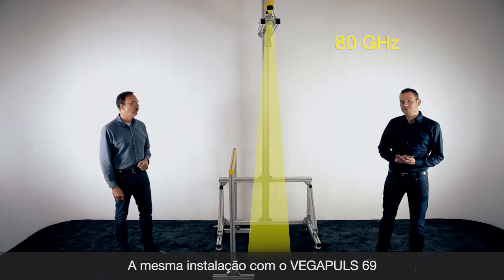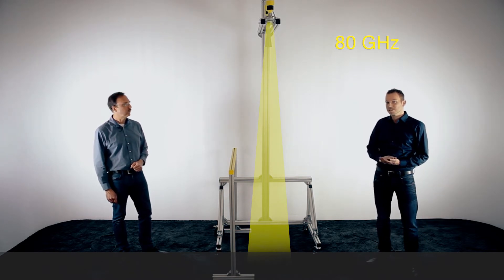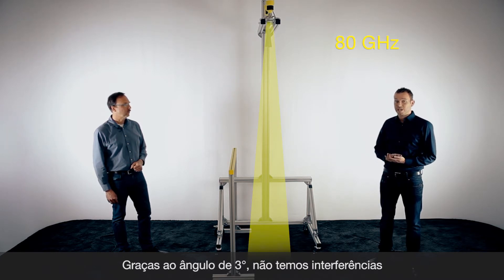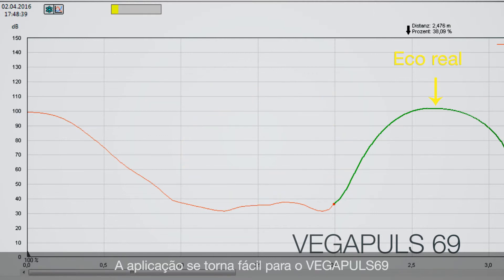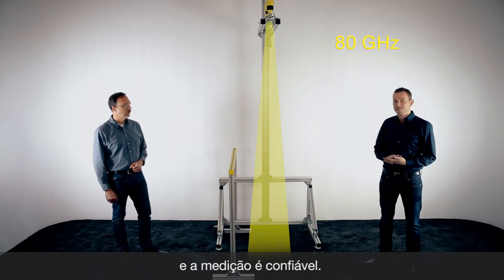Looking at the same situation with the VEGAPULS 69 and its three degree beam angle, you can see the beam is not hitting the metal piece and on the echo curve there is no false reflection. You have only the product echo. This metal piece is not disturbing the 80 gigahertz sensor — it has only one echo and that is the product. So it's a very easy measurement for the VEGAPULS 69.